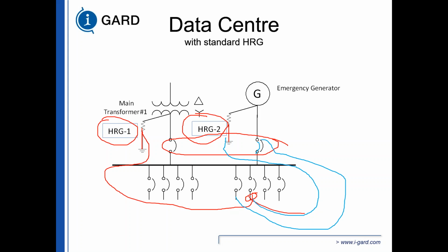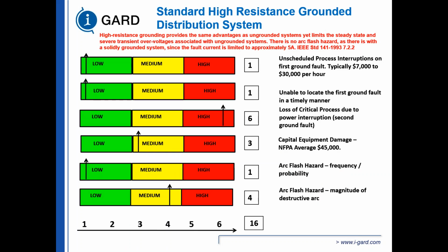You don't know what's going to shut down. It could be this breaker, it could be this breaker, or it could be the main, depending on how the relay coordination is set up. Capital expenditure is medium. Arc flash hazard frequency is lower because we employ a resistance grounding system. So we could say that NFPA 70E and Z462 have established that high resistance grounding is an arc flash mitigation technique simply because the probability of having a phase-to-phase or three-phase fault is quite low. And the arc flash hazard magnitude is medium.